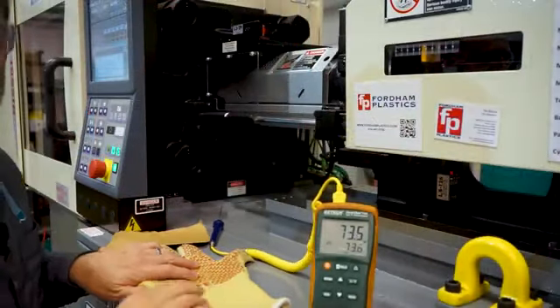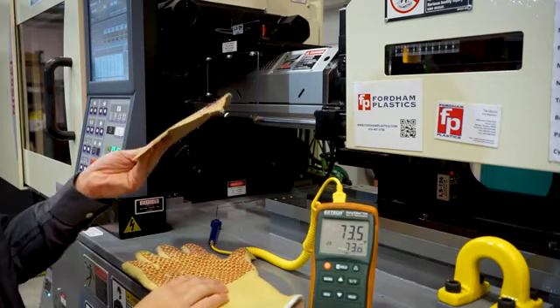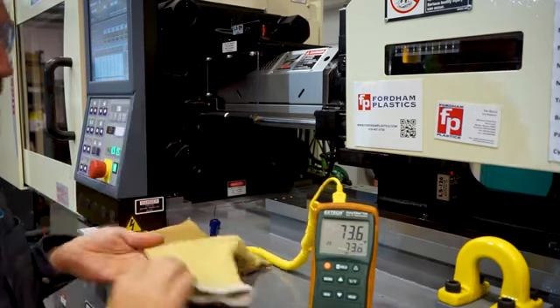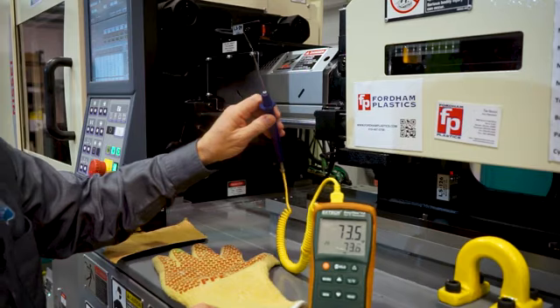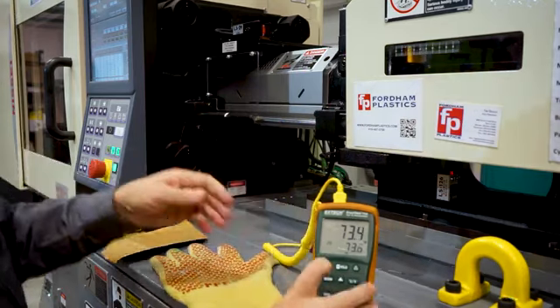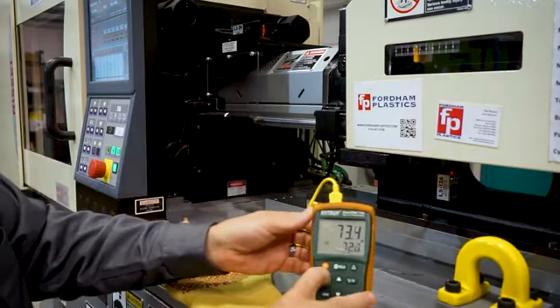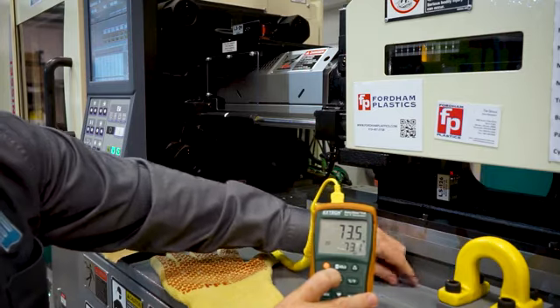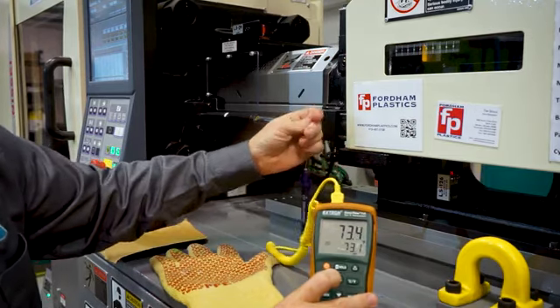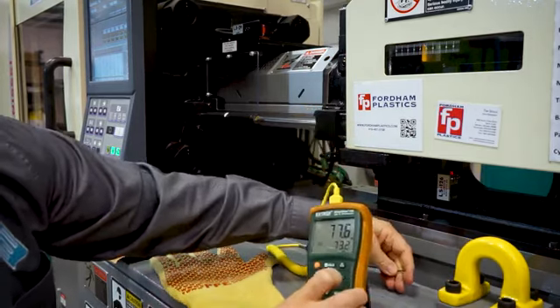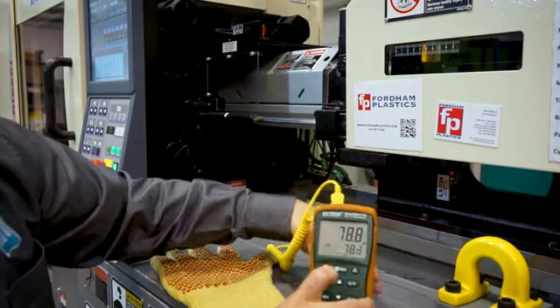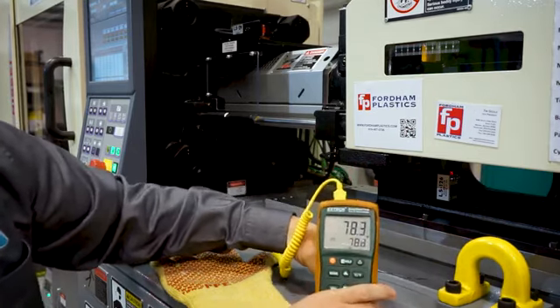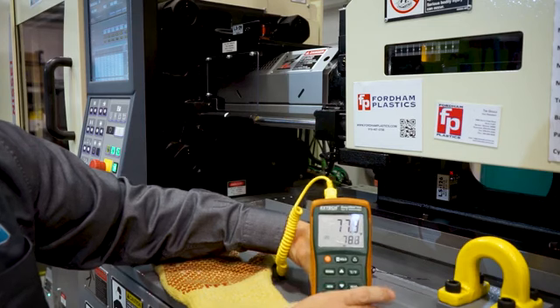So I have the machine set up and running. I have my piece of cardboard here, I have my glove, and I have my probe set up and ready. The machine's been running. I've hit the max button so that it will hold the max temperature. That way, if the temperature goes up and then goes back down, I do not have to worry about whether I saw the temperature or not. So I'm going to try to set that right there so you can see it.